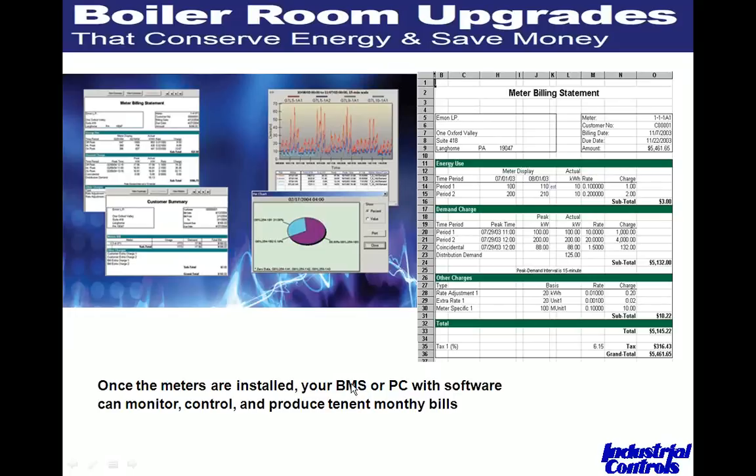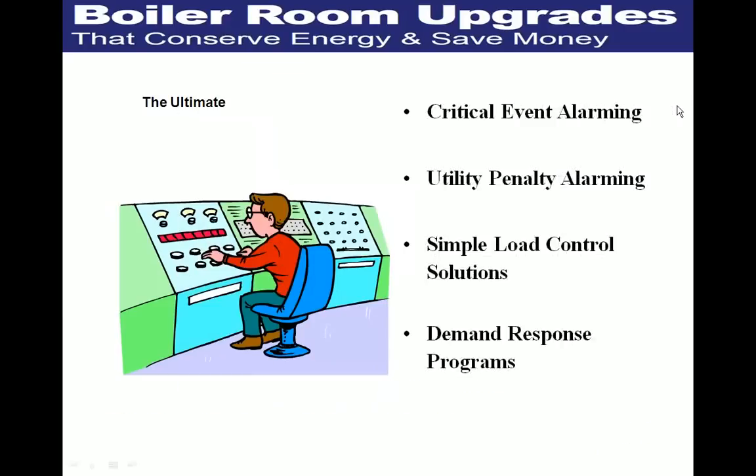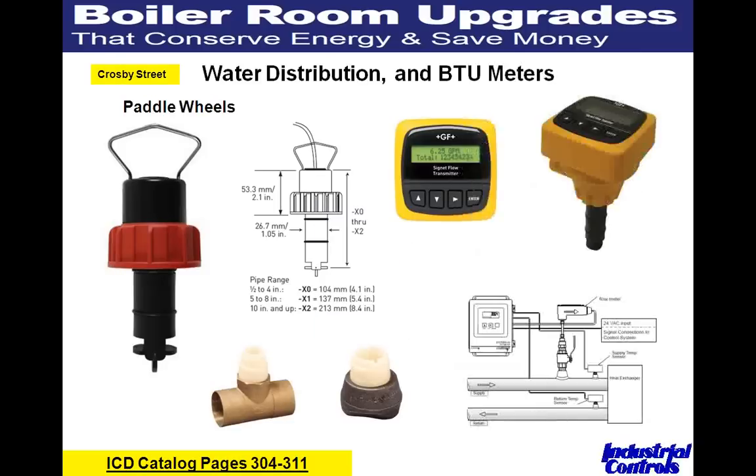Here are some of the graphics available with electric metering software. Once installed, you can bring data into your existing building management system, or use relatively inexpensive PC software to monitor, control, and produce tenant monthly billing statements. You can get a meter with just a local display, or one with outputs and Modbus RTU, BACnet, or LonWorks connections. The ultimate is integrating all submetering — electrical, steam, gas, water, and compressed air — into a BMS or DCS for trending, billing, utility penalty alarming, and demand-response programs that automatically turn off compressors, air handlers, or chillers to stay under peak load.